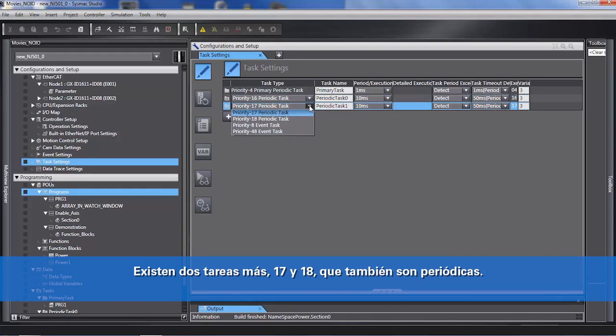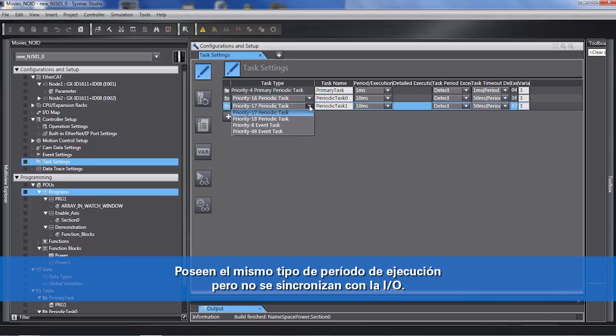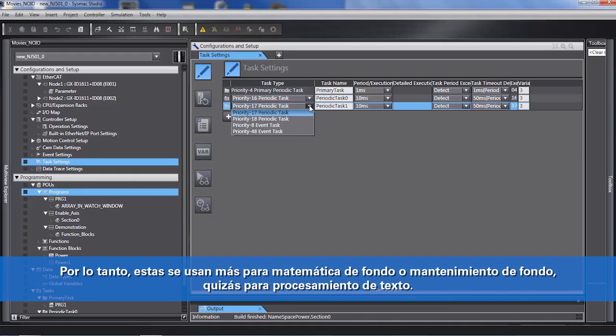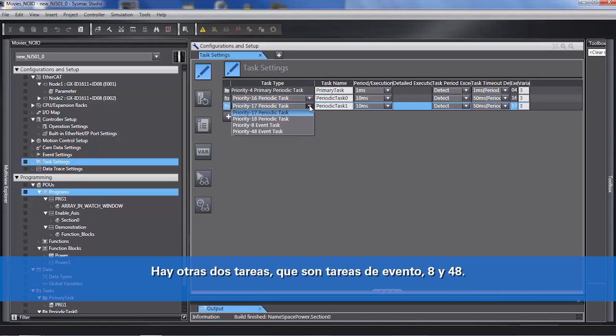There are two more tasks — 17 and 18 — which are also periodic. The same kind of period of execution, but they do not synchronize with the IO. So these tasks are used more for background math, background housekeeping, or maybe processing some text.